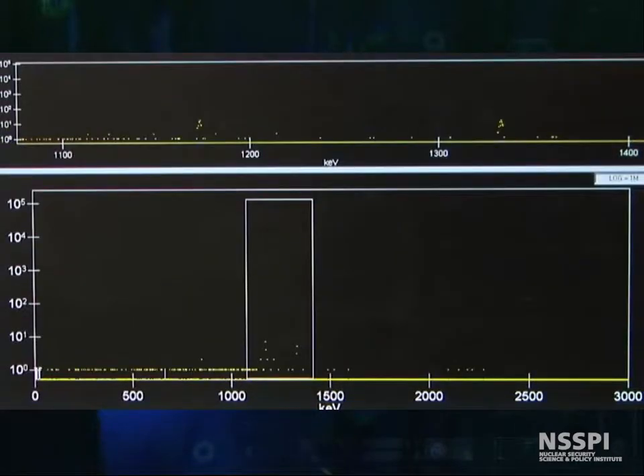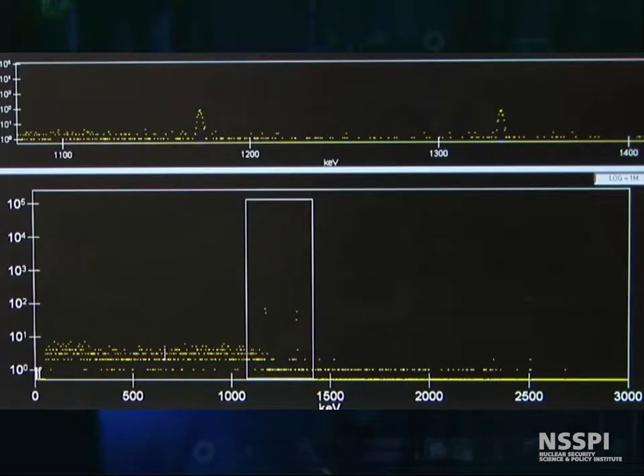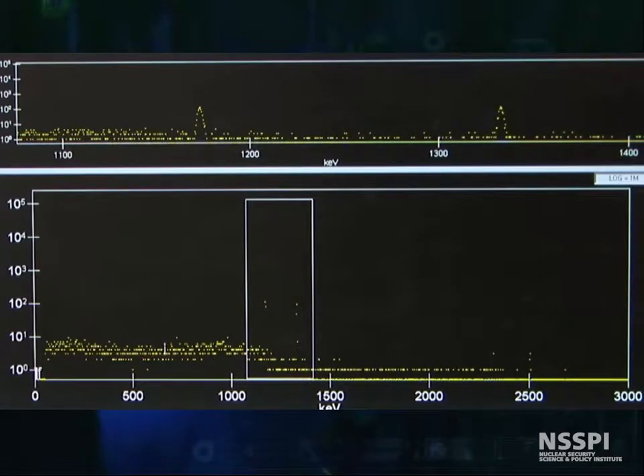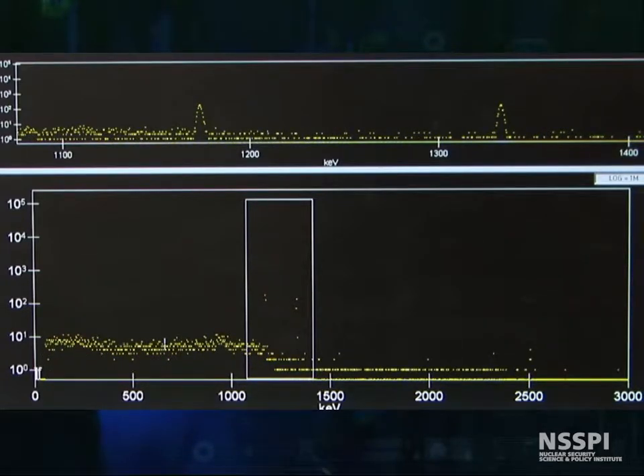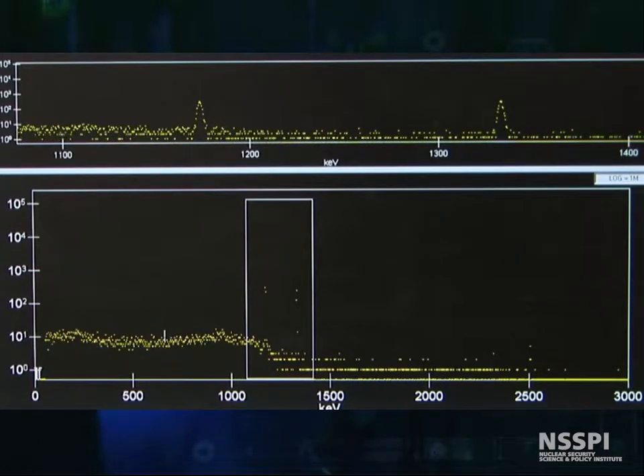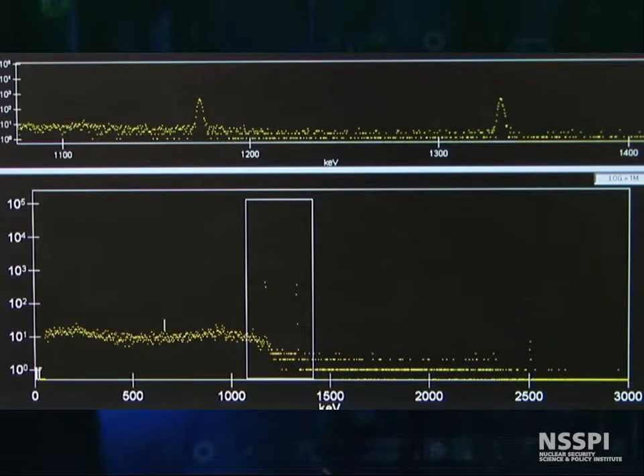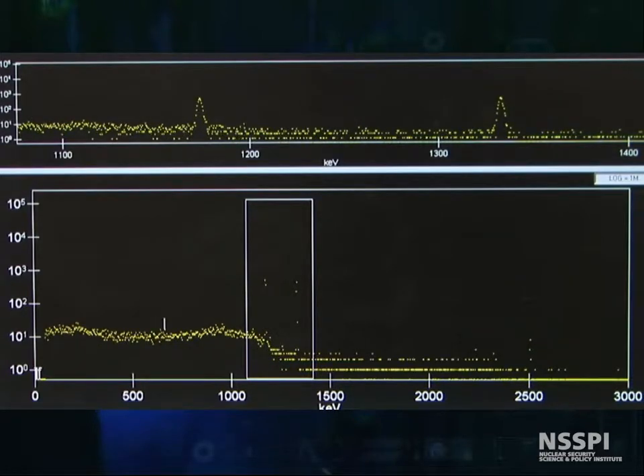As you can see here, the cobalt-60 is growing in. Here are the two peaks, and now they're fully resolved — they are clearly separated from each other. Notice how much better the resolution is here. Let's go add a cesium source to it, and then we'll watch the cesium grow in too.